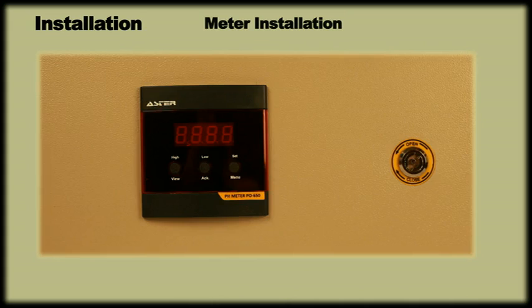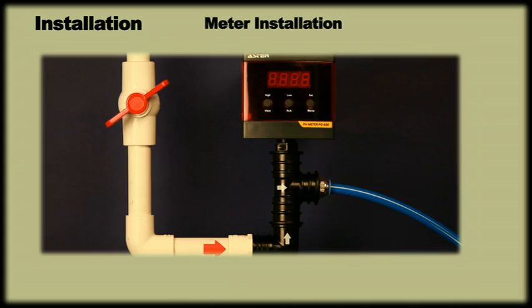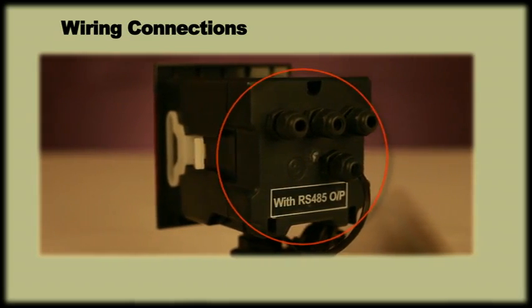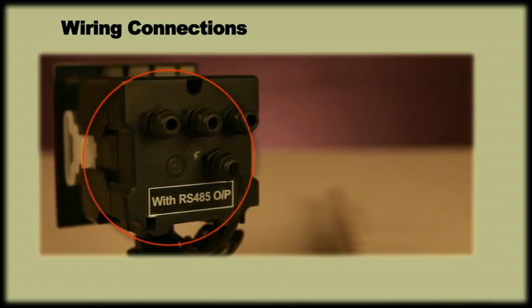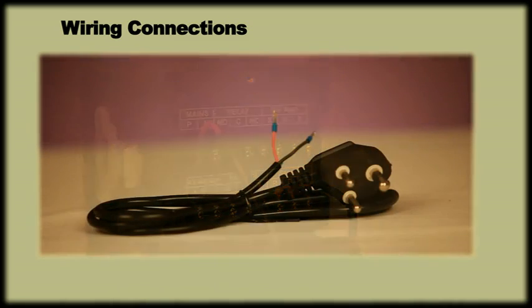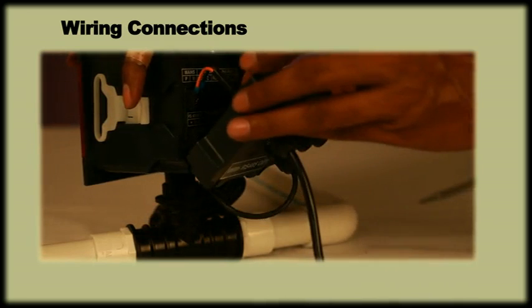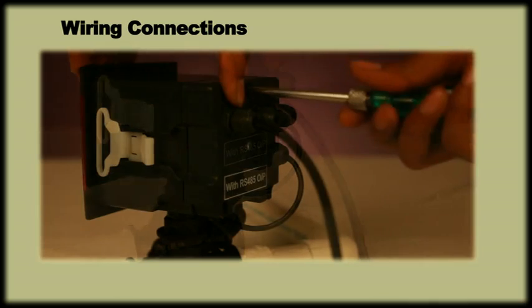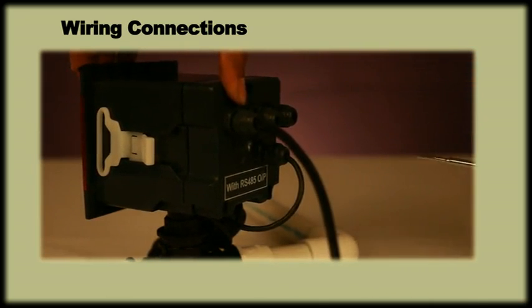Well that was all about the installation process. Now we shall see the wiring connection. Wiring connection: The meter has glands on the hinge cover to enroute the mains cable and output wires to their respective terminals. The supply voltage should be 230V AC plus or minus 10% unless specified. The cable used must be round and of 6-8mm in diameter. While closing the hinge cover, any extra length of cable has to be pulled out of the glands such that the hinge cover can be closed tightly, keeping it IP65.